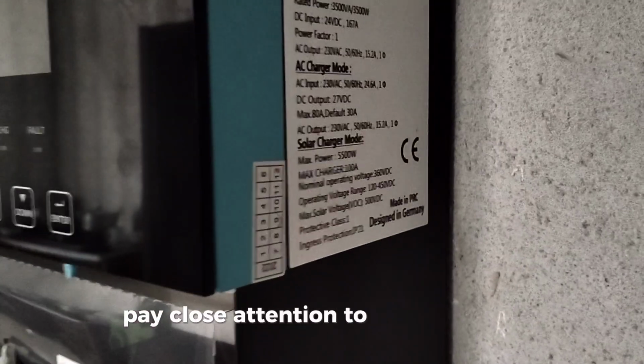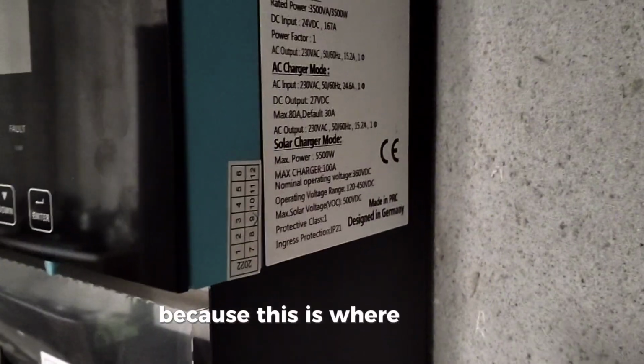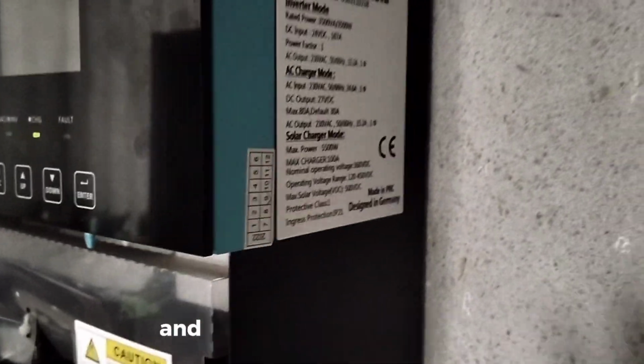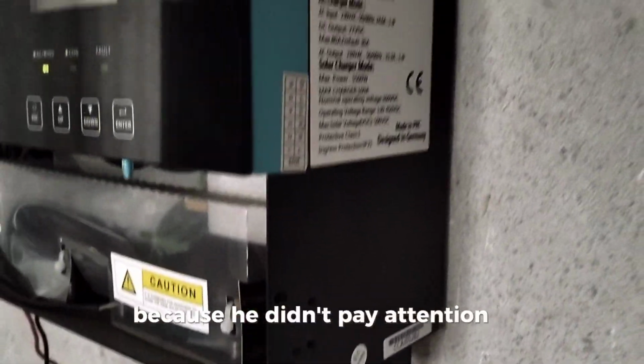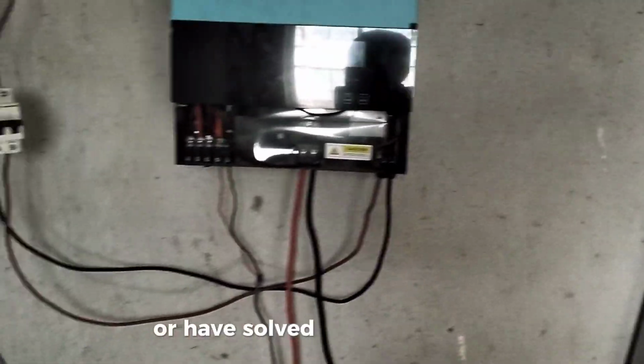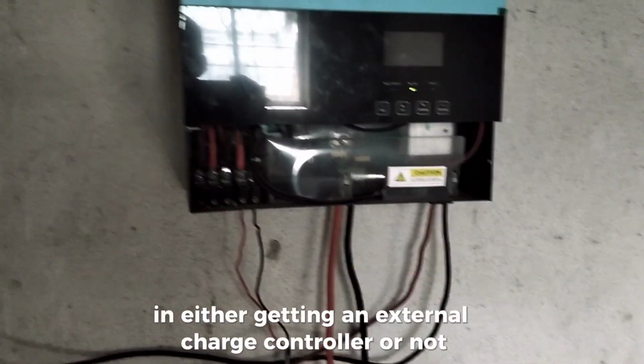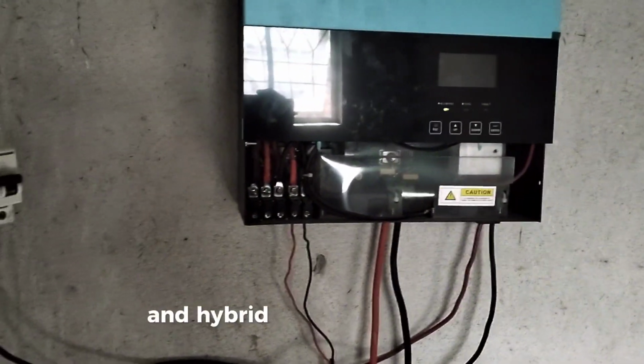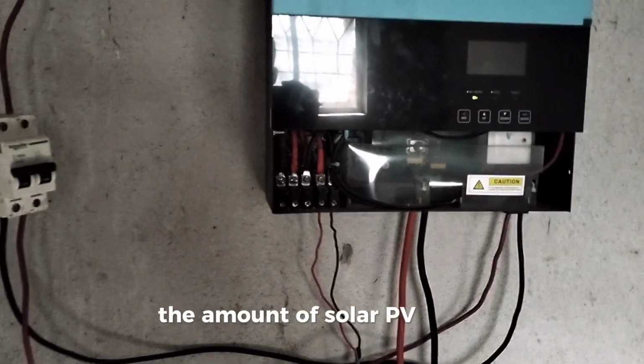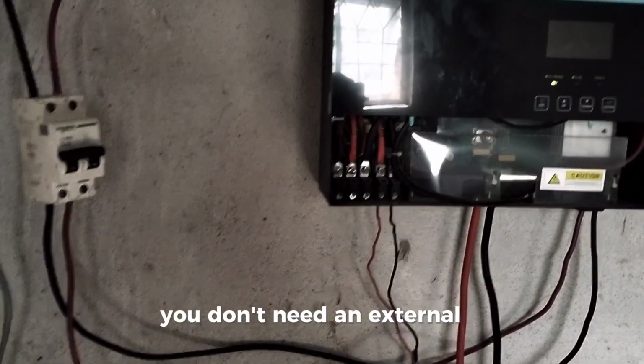Whatever the case, always pay close attention to the inverter specification, because this is where most installers make mistakes, ending up telling you your hybrid inverter isn't okay and that you need an external charge controller, simply because they didn't check the specification. I think this has solved your curiosity about getting an external charge controller or not — if your hybrid can handle the amount of solar PV you'll generate, you don't need one.